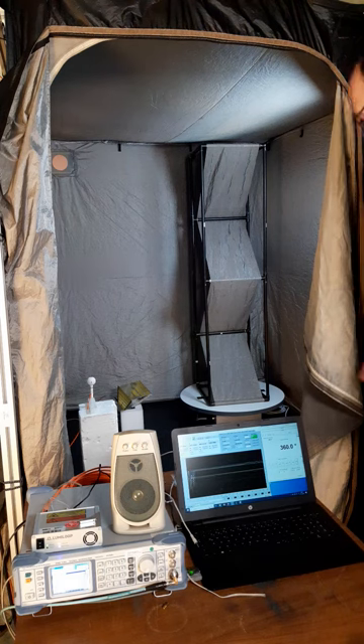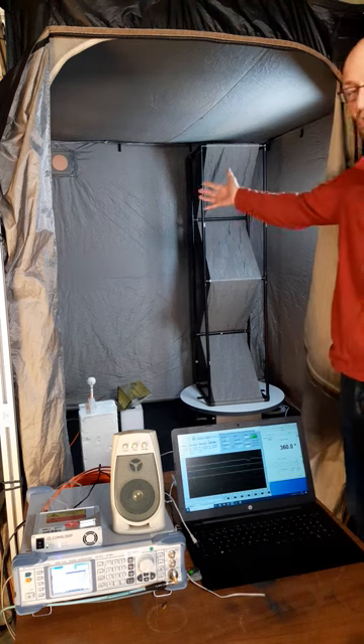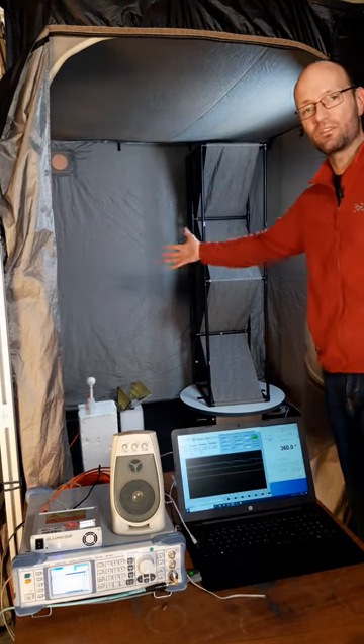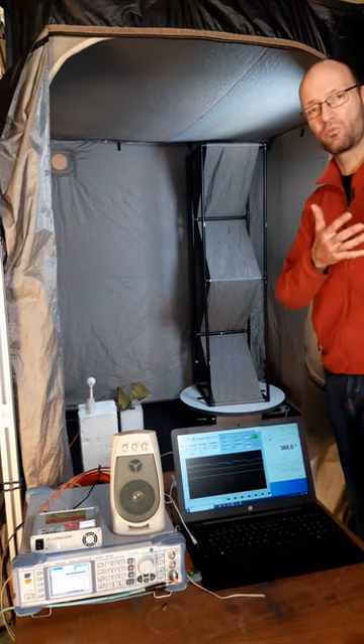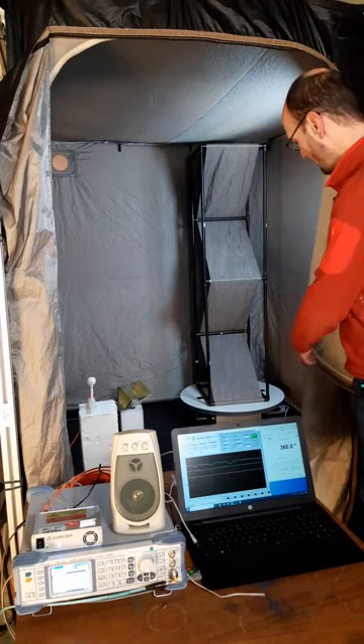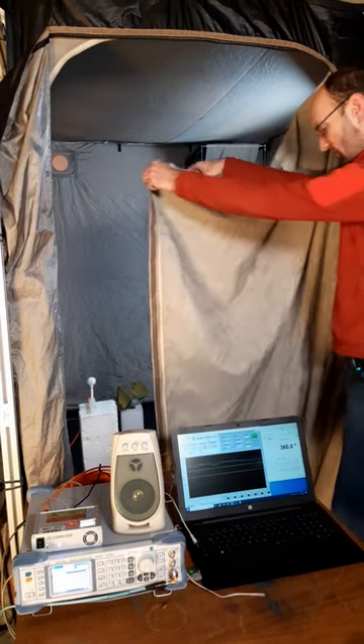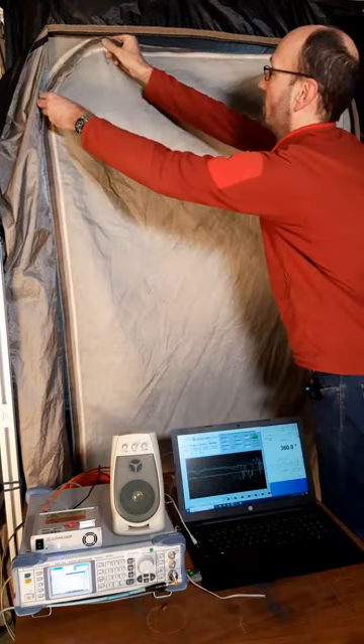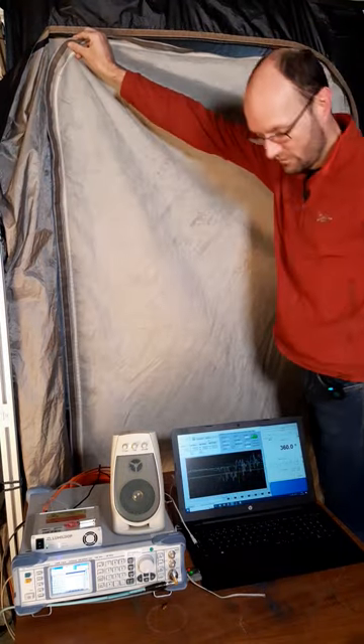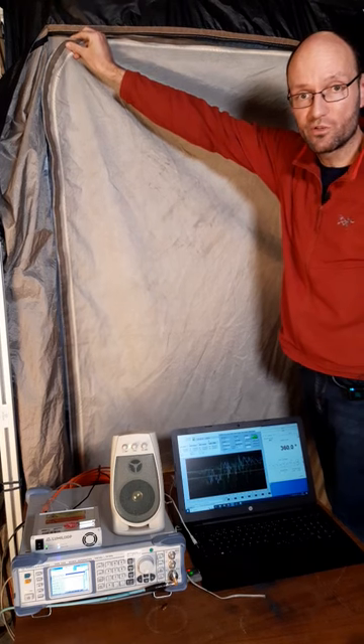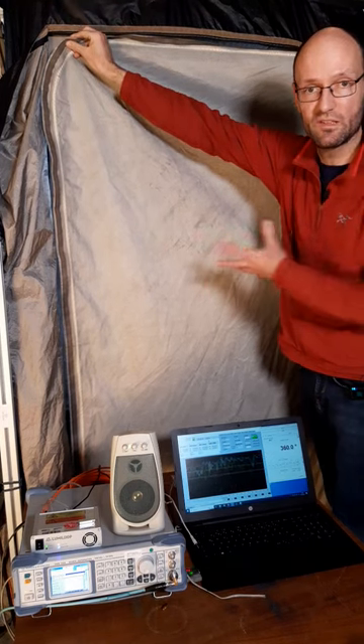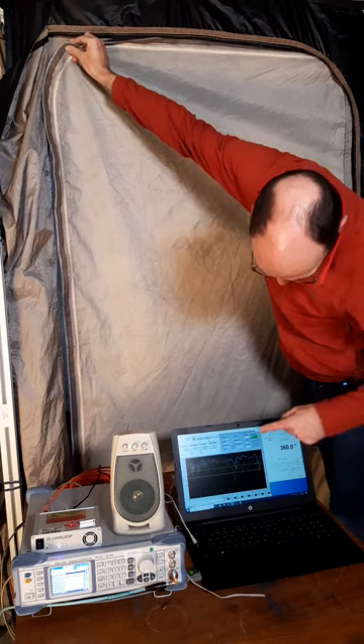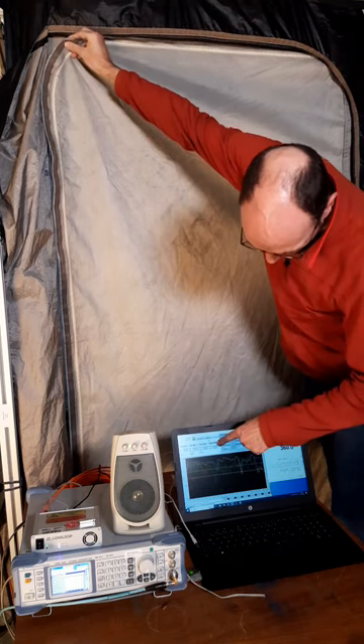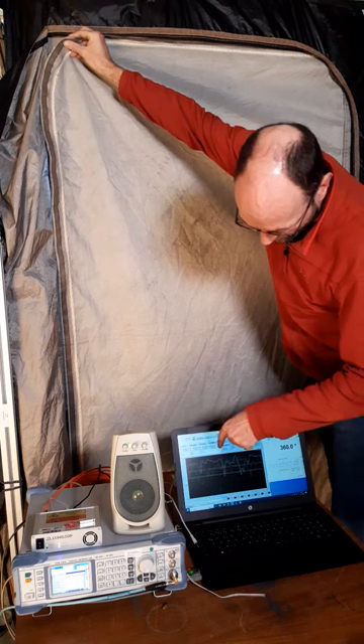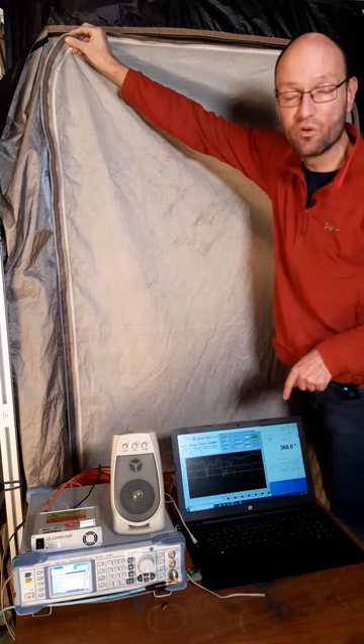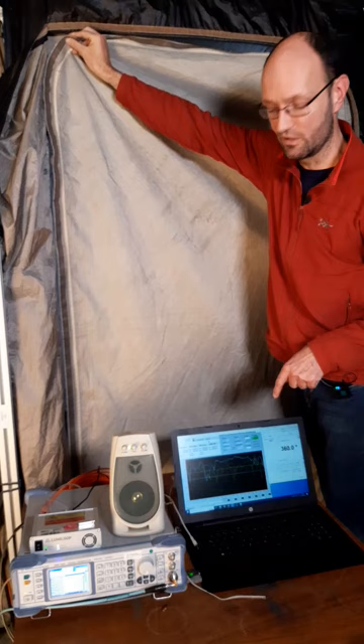One last thing I could show is, at the moment, lots of energy radiated by the antenna gets lost through this open door. If I try to close the door, at least a little bit, then I increase the quality factor of the chamber, lowering the losses inside because there are now more reflections, and the field strength now goes up to 3, 4, sometimes even 5 volts per meter, depending on the actual position.